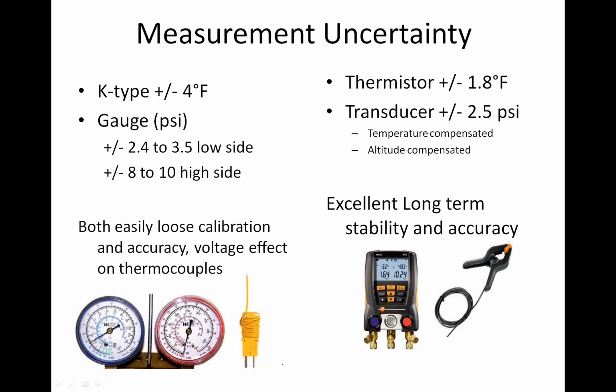And you also got to remember that Bourdon tube gauge has been bounced around the back of your truck. You tossed it in your 5-gallon bucket at the end of the day. Your K-type thermocouple could be affected by stray voltages. It could be you pulled a meter out of your truck that's hot, maybe 110 degrees, and you're putting it on top of the roof or setting it out in the ambient, and the cold junction and hot junction aren't the same temperature anymore. There's issues there that you have to make sure that you address with your measurement solution.